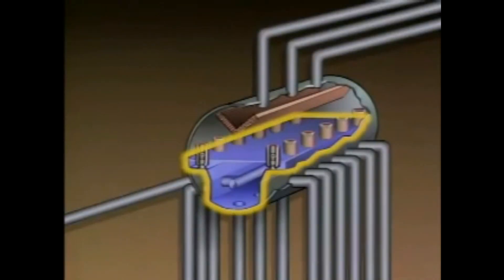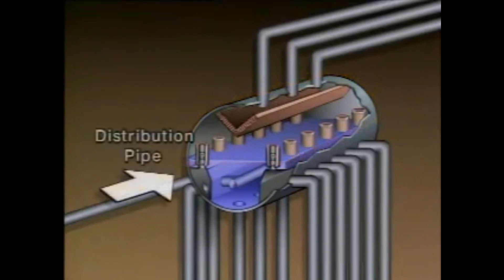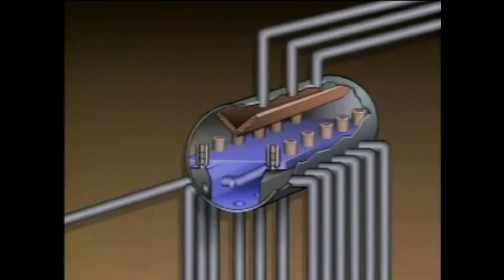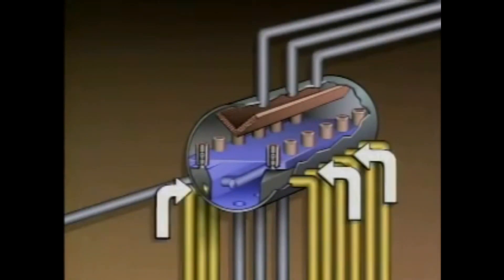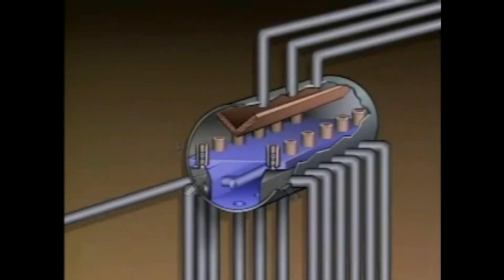The bottom part of the drum contains water to be circulated back through the boiler. The top part of the drum is used to collect steam. Heated feed water is fed into the drum through a distribution pipe. The drum is usually kept about half full of water. In this example, the mixture of water and steam that returns to the drum from the water walls is directed against baffles called drum shrouds that run the length of the drum.